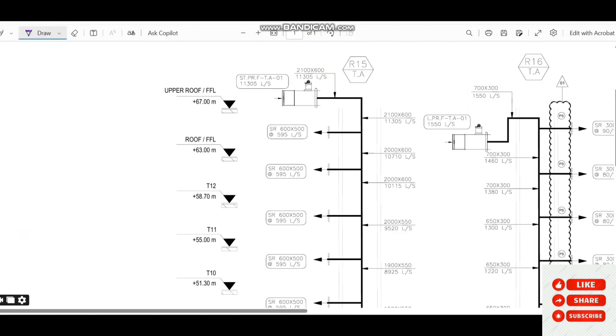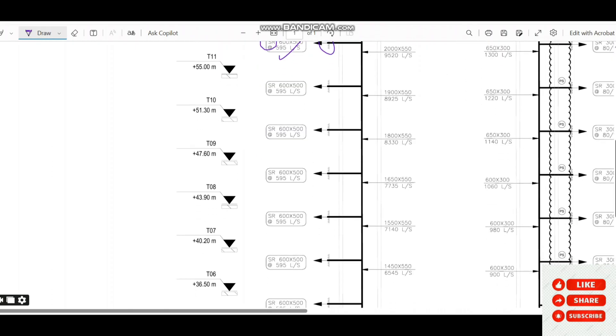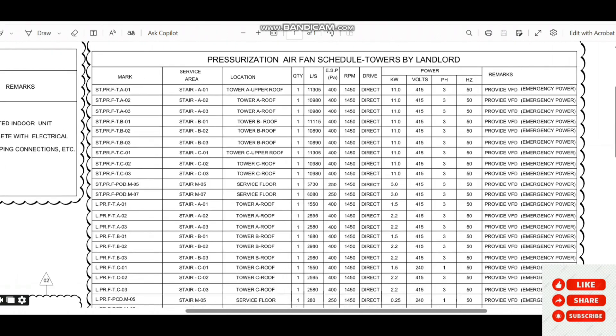The staircase pressurization fan, tagged ST.PR.F-T.A-01, has a capacity of 11,305 liters per second, which is equally distributed to all levels from top to bottom at 595 liters per second per level. SR (supply register) connections are provided at each level. A differential pressure switch is also located at mid-level of the stairwell to monitor and control the system.